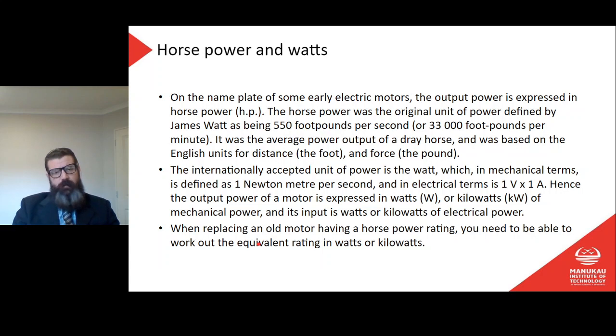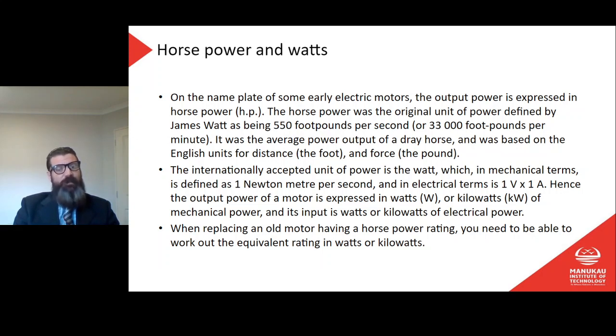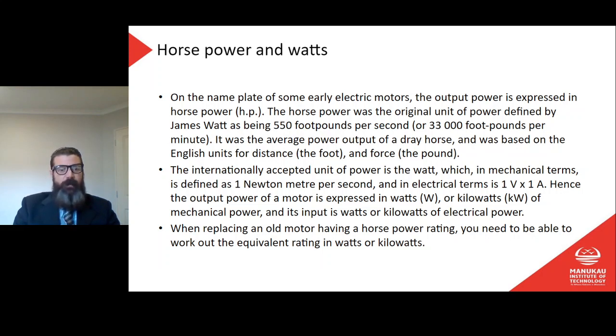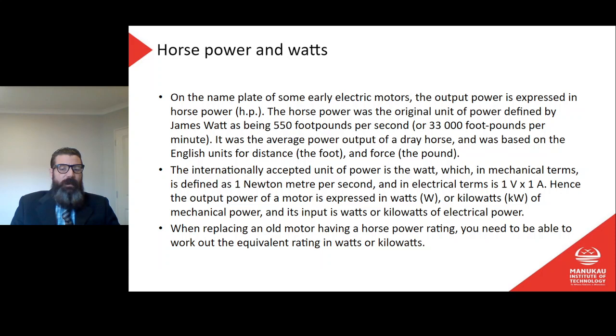On the nameplate of some early electric motors, the output power is expressed in horsepower. The horsepower is the original unit of power defined by James Watt as being 550 foot-pounds per second, or 33,000 foot-pounds per minute — the average power output of a dray horse, based on English units. The internationally accepted unit of power is the watt, which in mechanical terms is one Newton-meter per second, and in electrical terms is one volt times one amp. Hence, the output power of a motor is expressed in watts or kilowatts of mechanical power, and its input is watts or kilowatts of electrical power.